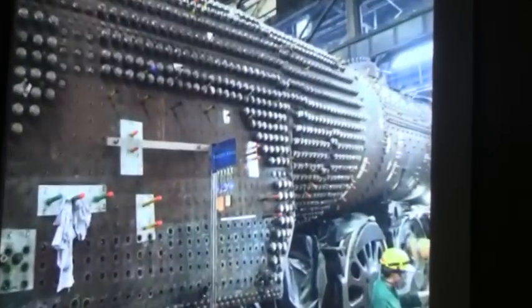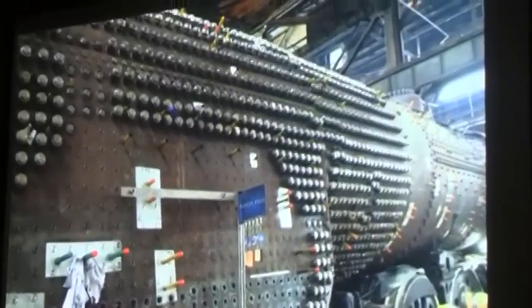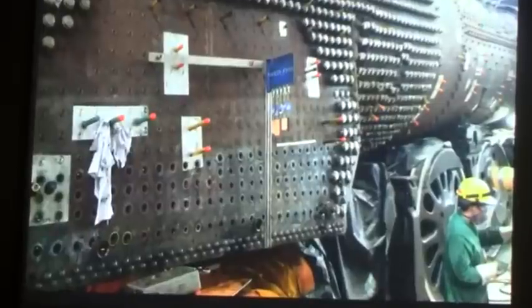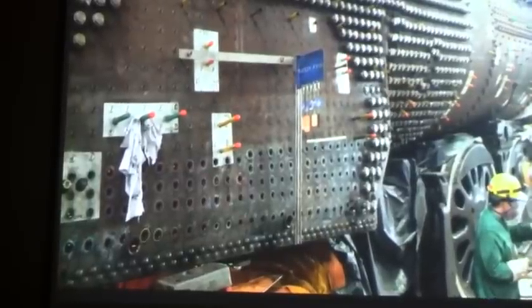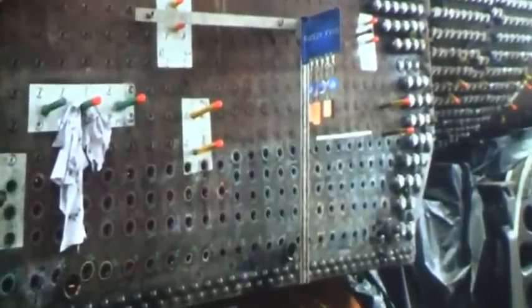Now the boiler's coming back together. Things are looking good, but you can see all of the stay bolts, 154 stay bolts on both sides, and all of the rivets down below, all the way around the backside. That was all behind the refractory, the fire brick inside the oil burning firebox. The worst, as I mentioned, the worst part of it was the water glass drains and what we call a telltale for the injector. An injector on a locomotive uses live steam to put water into the boiler.